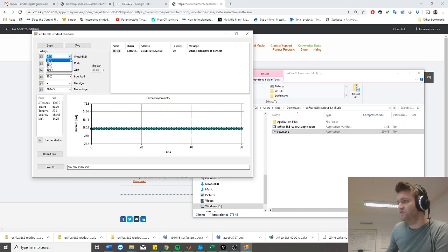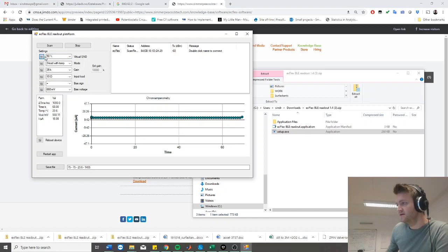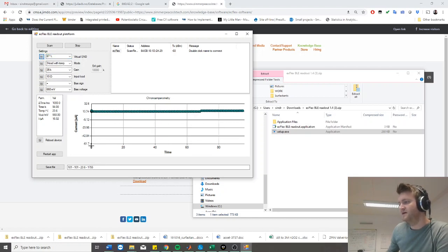You can change it up to, let's say, 50%, which means I'm going to send that setting to my EasyFlex, and that means that you allocate equally much to negative and positive currents. So you can see my outer bounds have changed to minus 47 and plus 47. If I expect primarily a negative current, I can step it up to 67%. And you can see that I have more availability on the negative side. So that's what virtual ground is about. Let's look at the next setting.